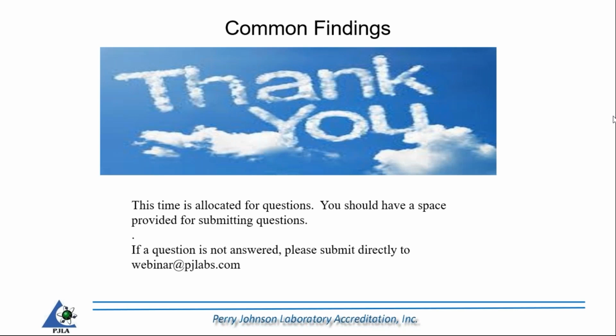Uncertainty budgets. Somebody's asking, what is the uncertainty budget, and does it apply to testing laboratories? We had some samples of uncertainty budgets here. It's specific to calibration, so it applies to calibration labs. It's where you basically identify the sources of uncertainty and you have to analyze them. With every uncertainty budget, there are three things I would typically see in there, and from there it just depends on the calibration. You always have the uncertainty associated with your reference standard, you always have uncertainty associated with repeatability, and you always have uncertainty associated with the resolution of the device under test.